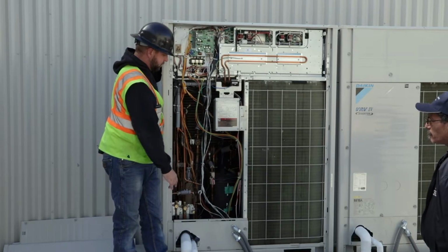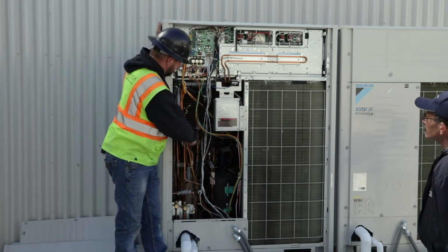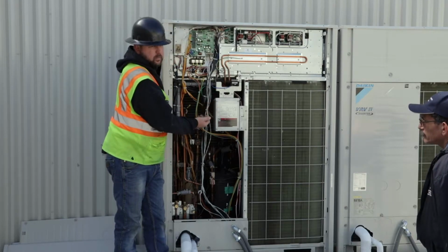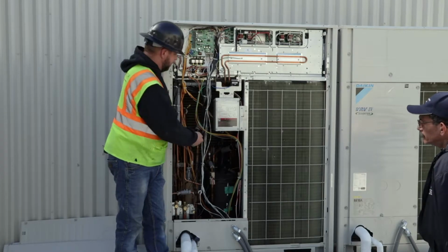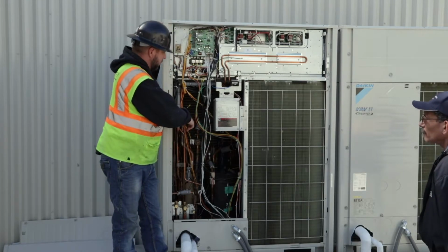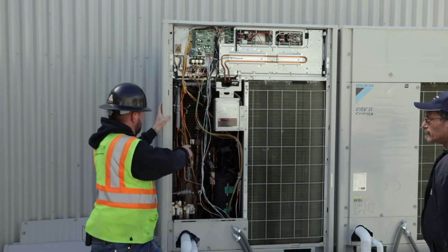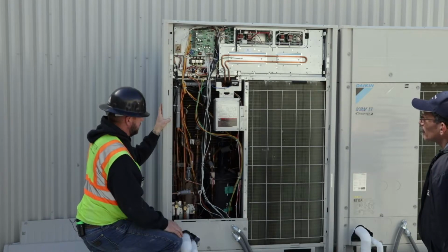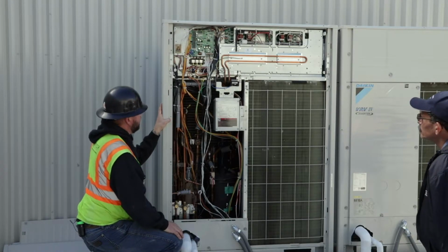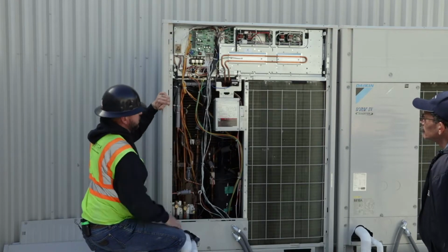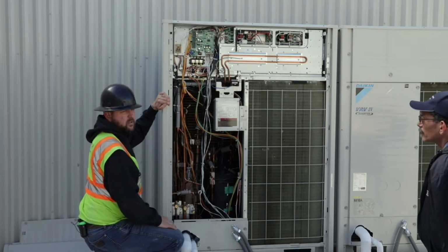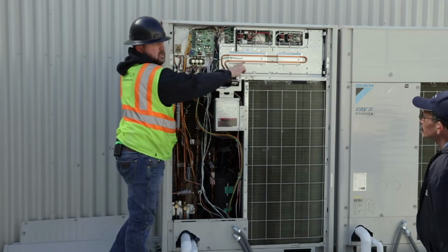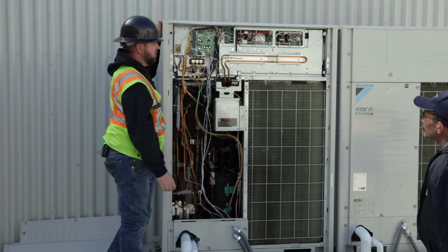So like I said, you've got your 2 compressors, and an accumulator back there to help bring your refrigerant back from a liquid state to a vapor state, and then your oil separators back there as well. Other than that, you've got your 2 condenser fan motors, inverter driven as well. Right here is a subcooler to keep all your inverters cool as well.